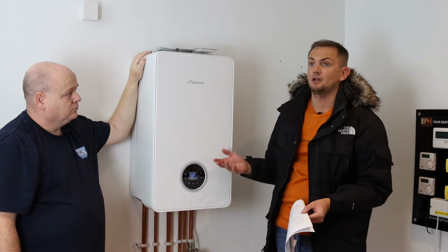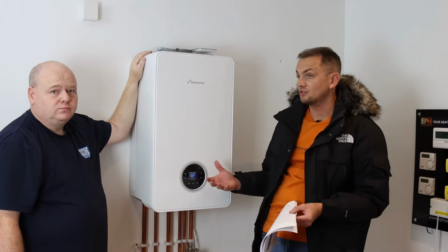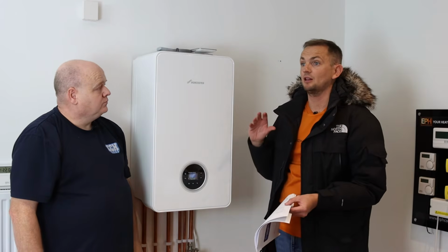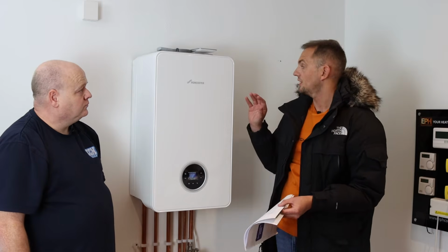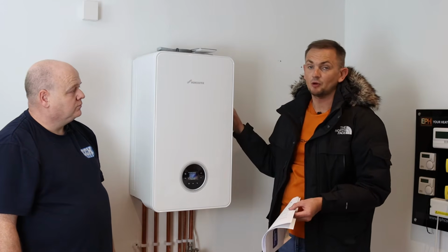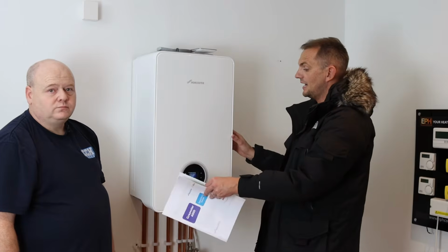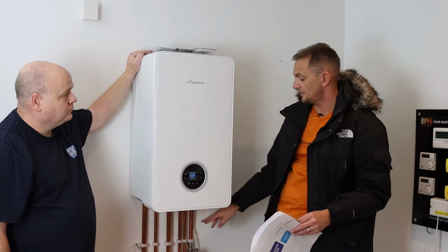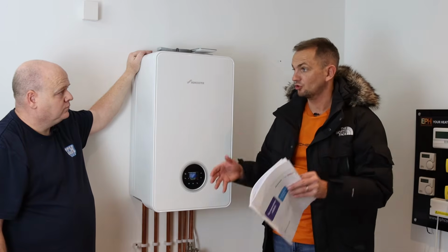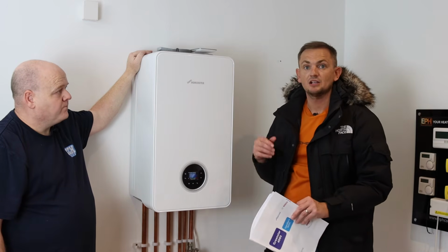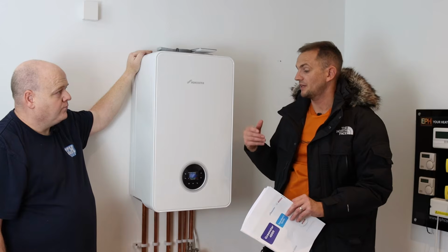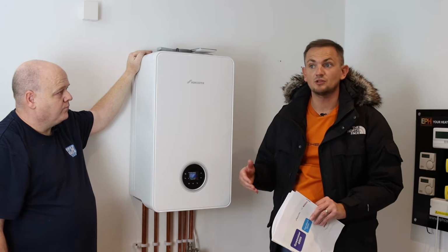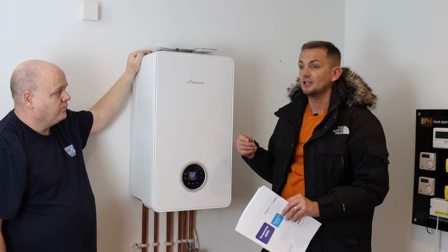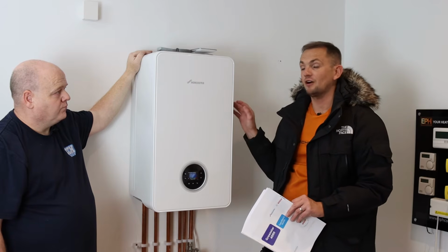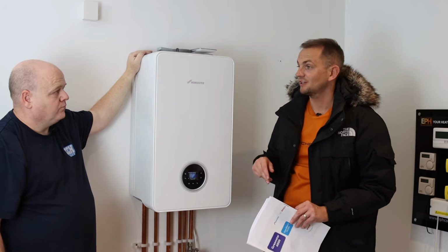Something else on the product as well, from an install perspective, that we've noticed is we get a lot of good feedback around the jig's nice and easy to pipe up. So the jig essentially behind this whole product would pull off this frame. There's a frame behind here that you pipe up first, and the boiler just sort of clicks on and tightens up, doesn't it? So nice and easy. And again, for future replacements, if you stick with this style product, this actual boiler will fit on the old iJunior jig.